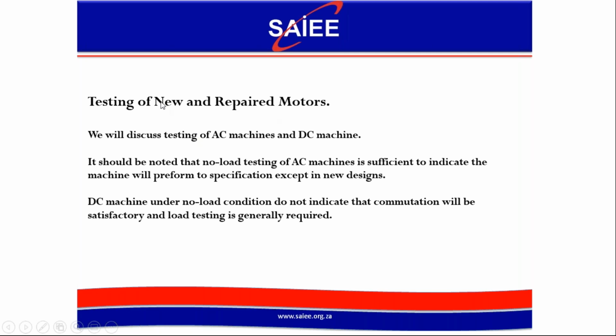Testing of new and repaired machines. We'll discuss AC machine and DC machine testing. It should be noted that no load testing, locked rotor testing, and winding insulation testing is generally sufficient to prove that the repaired machine or the new machine will meet the requirements, except of course in some new designs where you may want to do some full load tests on the machine. There are a number of companies in the country which do full load tests on AC machines.